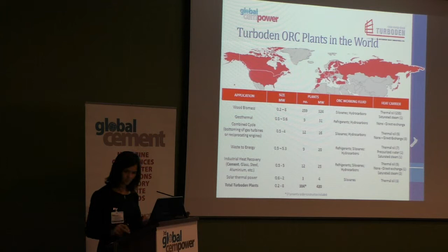Regarding working fluids, we have wide experience with different kinds, across the three families we presented before. We've used up to nine different working fluids so far, so we have the capability to select the proper working fluid for the specific application. We're also flexible with heat carriers—we've designed ORCs fed by thermal oil, saturated steam, pressurized water, and we also have units that use the exhaust gas directly, without any heat carrier loop.